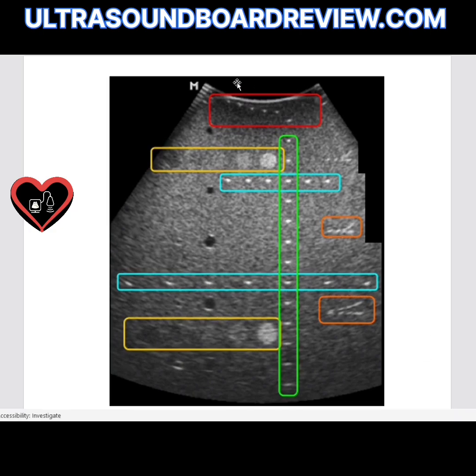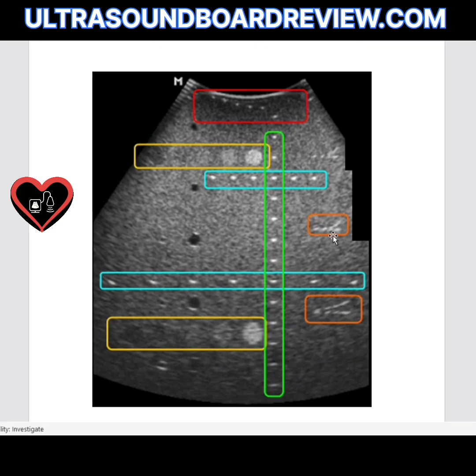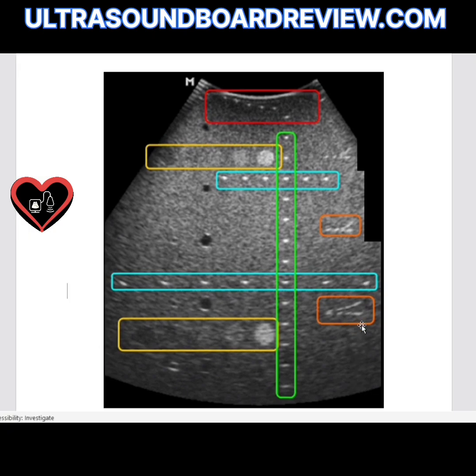We've covered the dead zone, contrast/dynamic range or grayscale, and horizontal and vertical calibration — but which ones will actually calibrate the axial and lateral resolution? We're down to one more color. These will both evaluate your axial and lateral resolution depending on which way the beam is going. If the beam is coming from top to bottom, it's evaluating axial resolution — you can see two little dots with spaces in between, determining whether the system can resolve one or two dots. The axial resolution or SPL may be too large for the space.